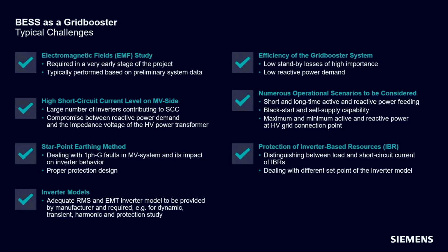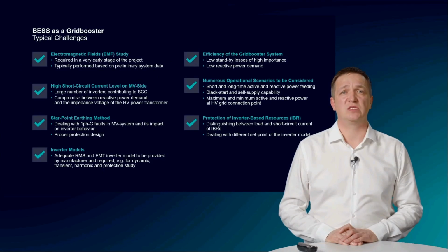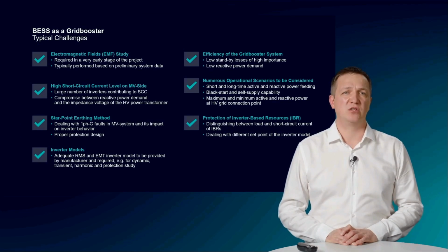Their verification is performed in an RMS and EMT software. Both of them require validated inverter models which can reproduce the short circuit current contribution of the inverter as realistically as possible. The challenge in protecting inverter-based resources is that the maximum short circuit current contribution lies almost in the same range as the maximum load current. Especially in case of unbalanced faults, there are differences to be expected between conventional, so synchronous machine-based, and inverter-based resources.